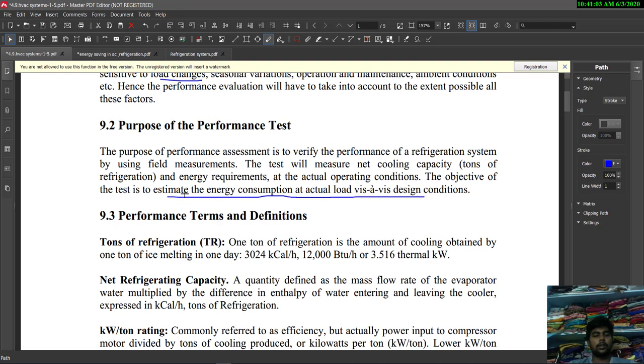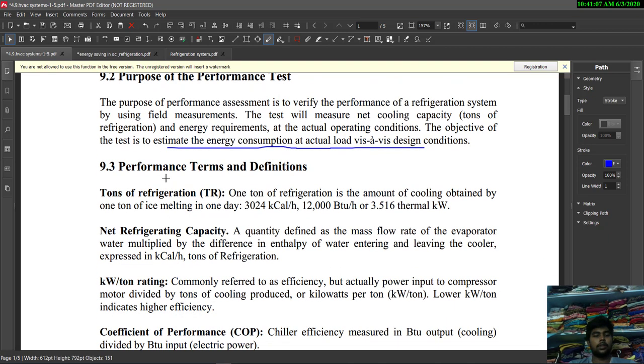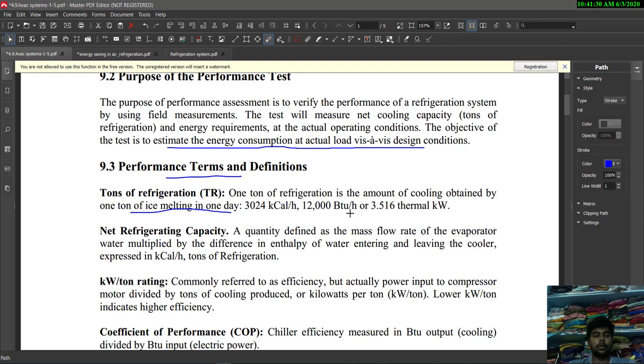Next we will see performance terms and definitions. Tons of refrigeration: one ton of refrigeration is the amount of cooling obtained by one ton of ice melting in one day, which is equal to 3024 kilocalories per hour, 12000 BTU per hour, or 3.516 thermal kilowatts.